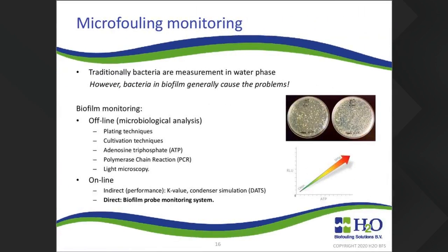To monitor the other type of biofouling, microfouling, bacteria, traditionally they are measured in water phase. Usually most of the analyses present are done in the water phase of a system, while bacteria in a biofilm cause a real problem, like MIC or Legionella. So you need to look at the biofilm and monitor the biofilm. That can be done offline through microbiology analysis, which generally takes time and is costly, but you can also do it online using a biofilm probe monitoring system.